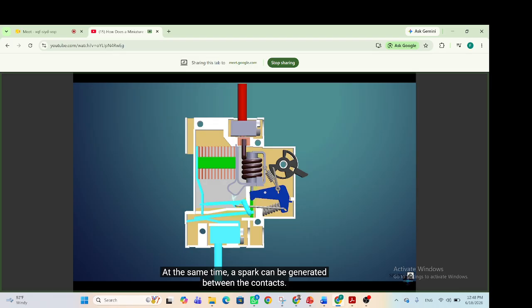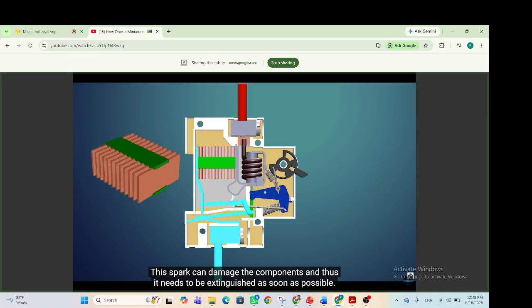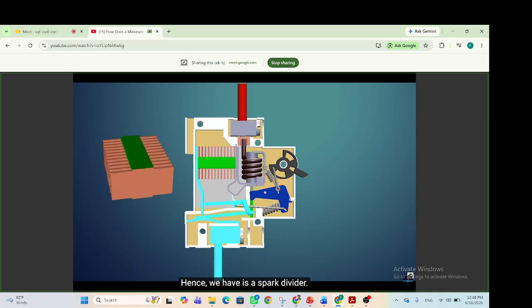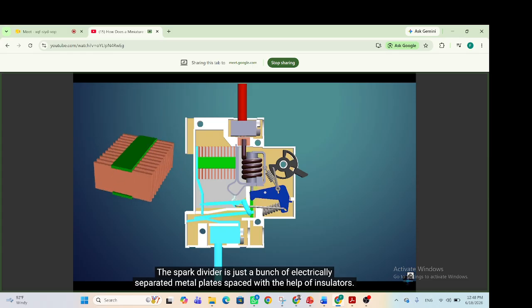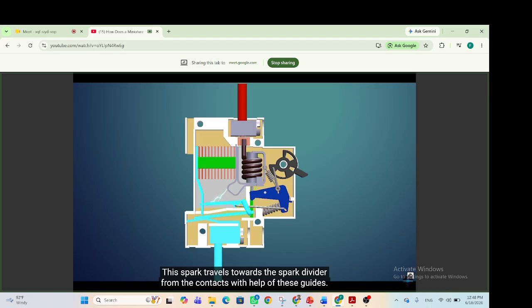At the same time, a spark can be generated between the contacts. This spark can damage the components, so it needs to be extinguished as soon as possible. Hence we have a spark divider, which is just a bunch of electrically separated metal plates spaced with insulators. The spark travels toward the spark divider from the contacts with the help of guides, shaped so that the spark travels toward the divider.